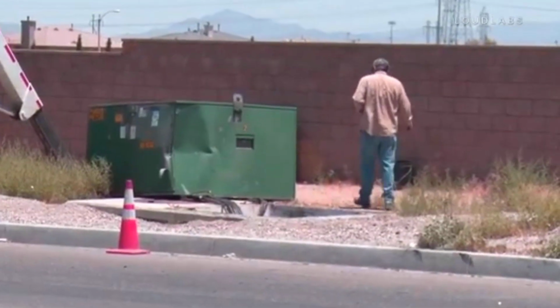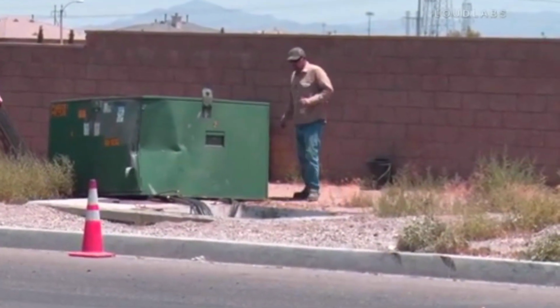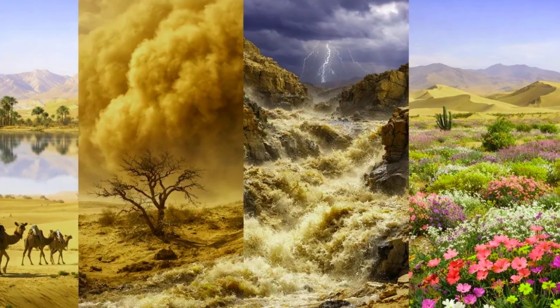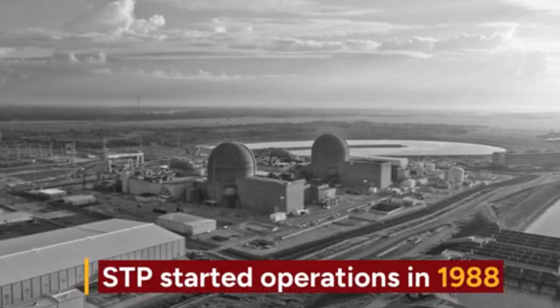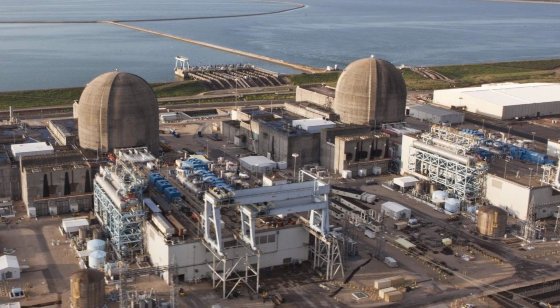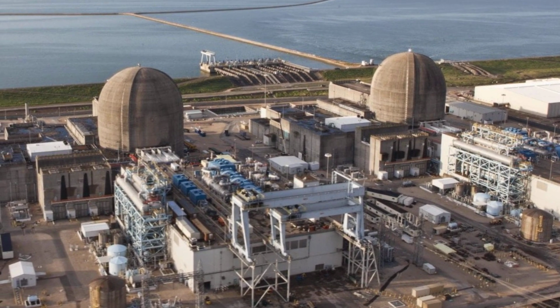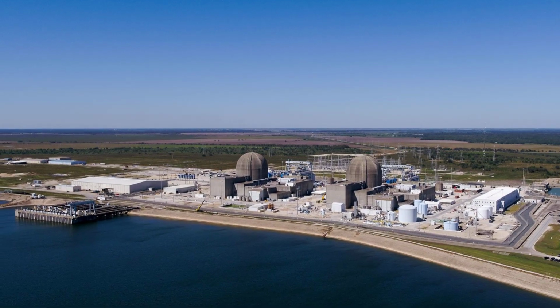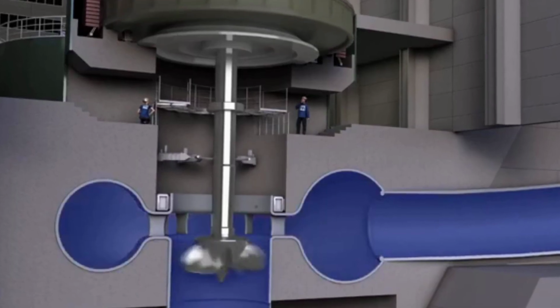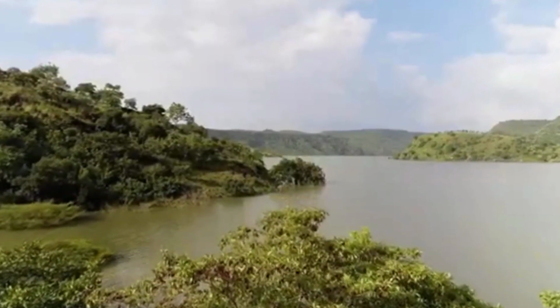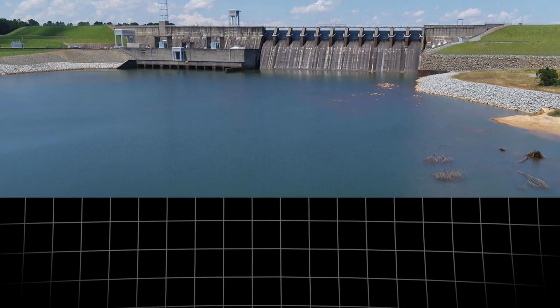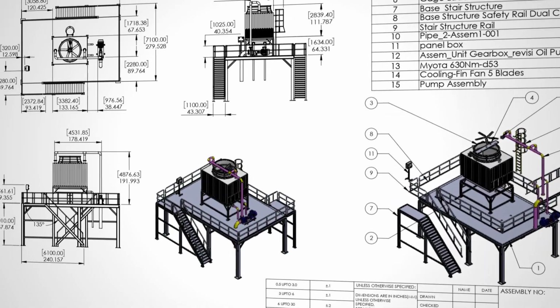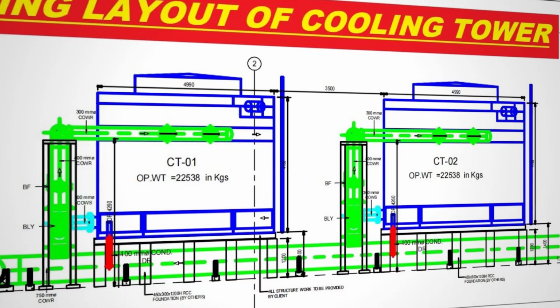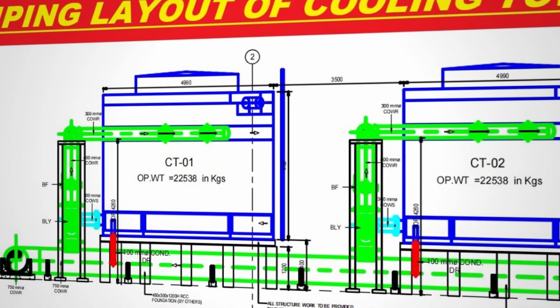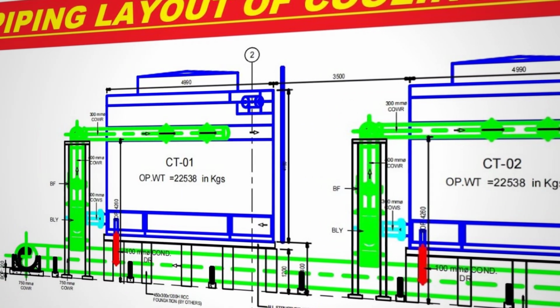Even if dry air allows for significant evaporative cooling, the air may not become buoyant enough to naturally rise within the tower. For instance, both nuclear plants in Texas utilize large reservoirs for cooling. This illustrates the immense cost considerations in power plant feedwater cooling. In these cases, constructing and maintaining a dam and a vast lake proved more economical than building a cooling tower suitable for that climate. While that delves into some intricate details, it underscores the fascinating depth of engineering involved in such structures, and we've only just scratched the surface.